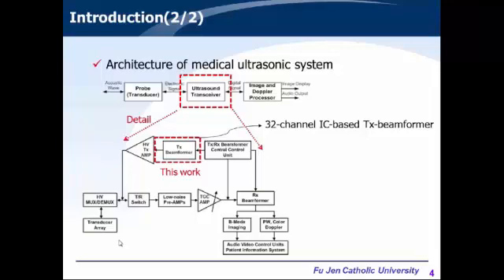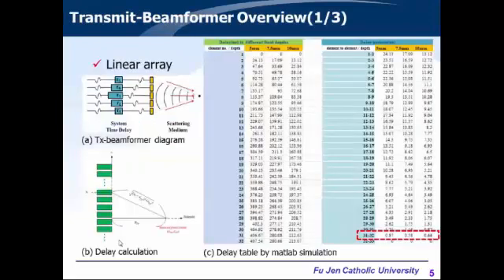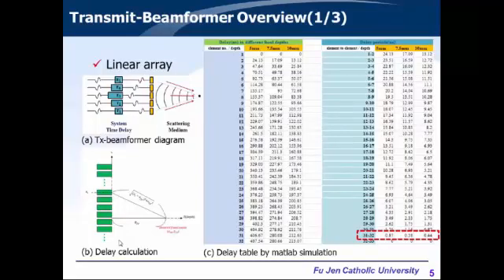Here is the architecture of the medical ultrasound system. We focus on designing this transmitted beamforming, which is a 32-channel IC-based transmitted beamformer. We use it to control the delay time for the elements of the transducer array. The purpose of transmitted beamforming is to apply the appropriate delay time to transmitted pulses so that each signal arrives at the focal point at the same time.